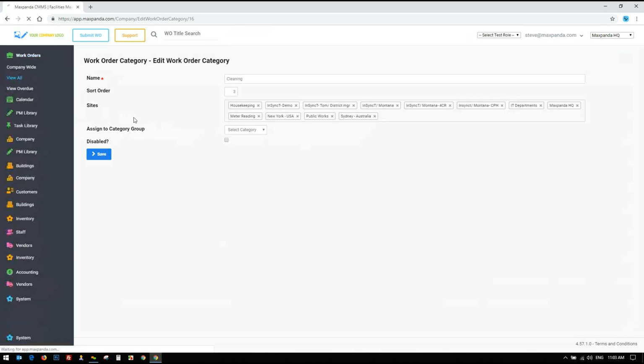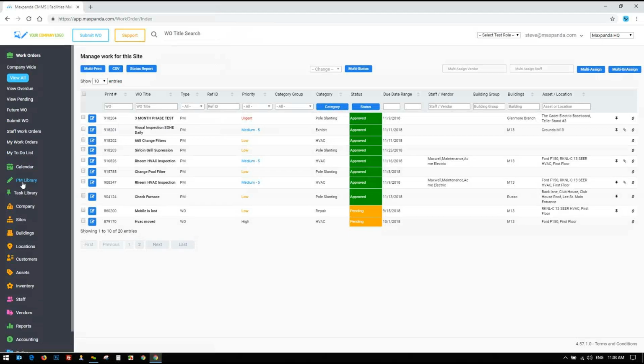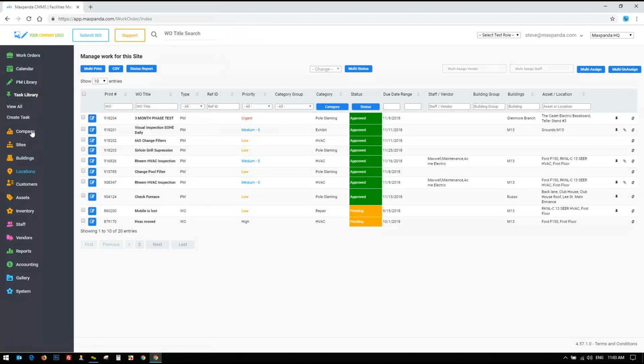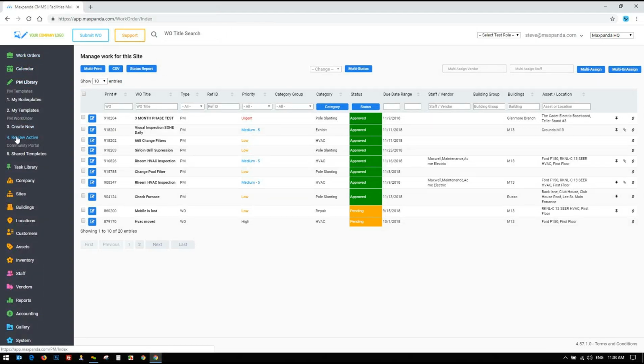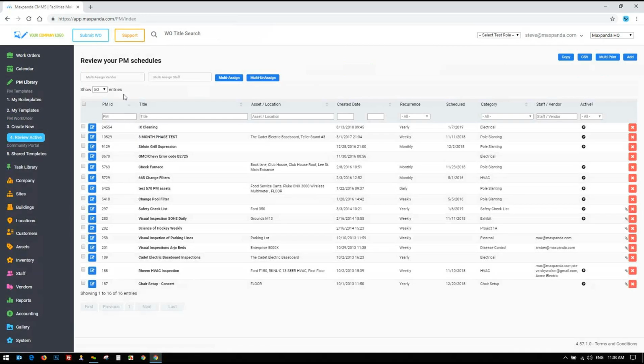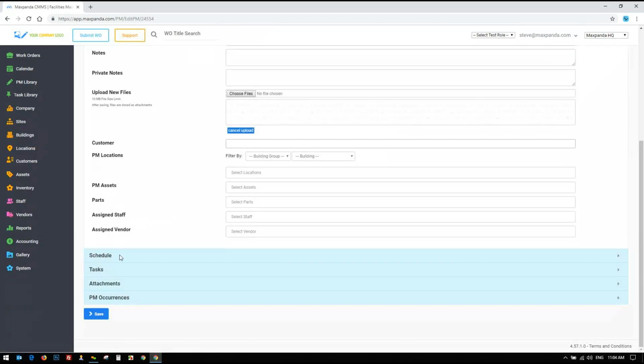Well, we'd have to put a task of calibration and say kick off from that calibration, because say within that 30 days it broke and somebody came in and fixed it, and once they got done fixing it, they would calibrate to check it. That's going to reset the PM. It wasn't really due for PM. It was being calibrated because it was repaired, but because they did that calibration on it, that is going to re-kick the PMs again.